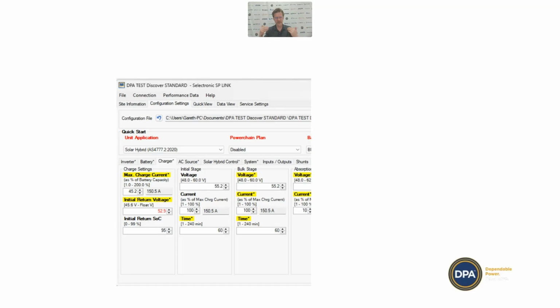What we found when testing the Helios with the Selectronic is that, unlike other inverters, it's going to trip out if it's above 150 amps. It won't do it straight away, but if you run it for half an hour at around 160, eventually it's going to trip. The guys from Selectronic also explained to me there's a difference between magnetic and thermal style breakers, and I don't quite 100% understand how that affects the charge curve. But the short story is that 150 amps per Helios battery is your maximum charge current. Everything else in the wizard is set up fine, and you can just use those values.